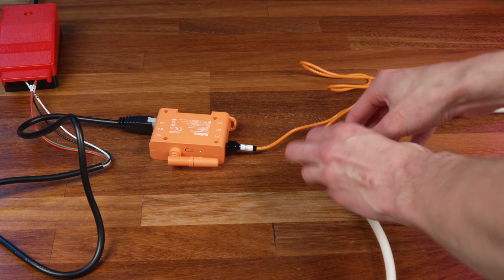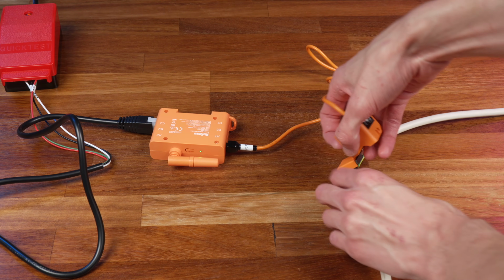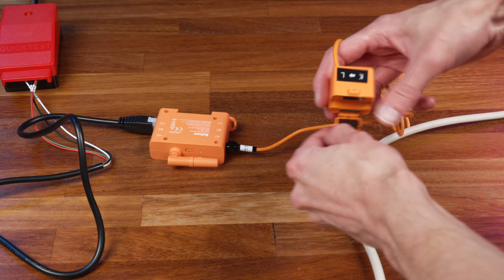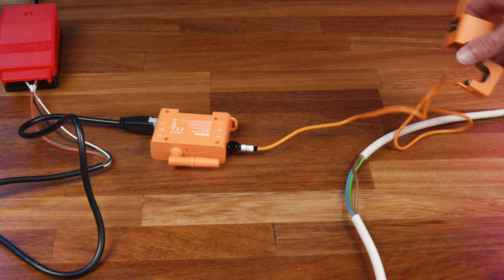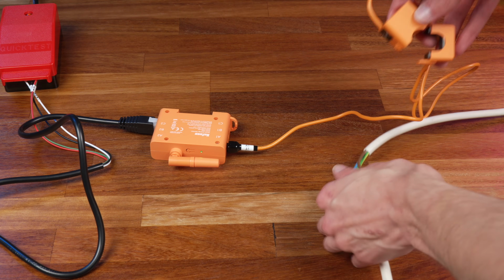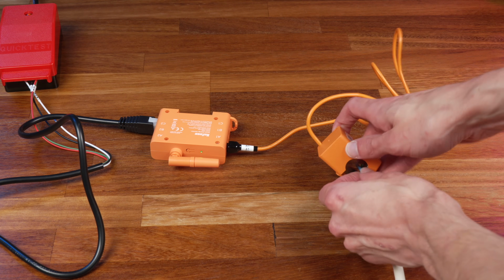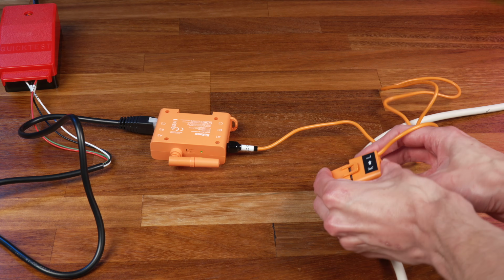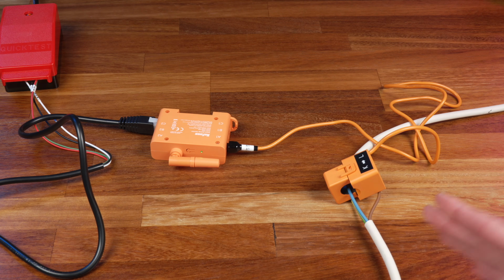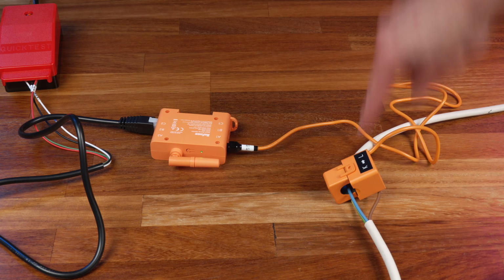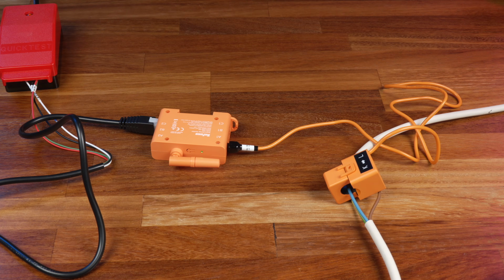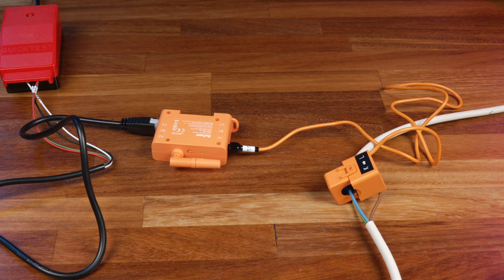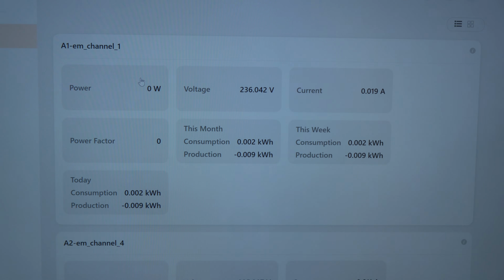Similarly, if we wanted to, we can move the CT onto the neutral. So we can take it off the line there and put it on the neutral. And because the current's flowing in the opposite way down the neutral, we need to install the CT in the opposite direction. So we install that around the neutral that way. And as we can see, we now have it so that the current flow is pointing away from the device and back to the source.